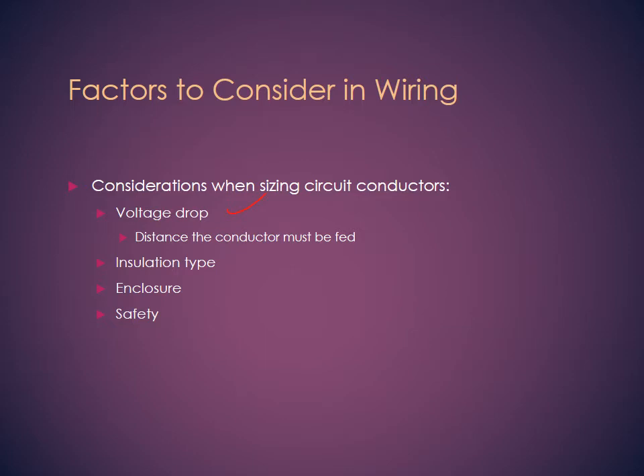We said 14 gauge mostly. Next, voltage drop. Voltage drop depends on the distance of the conductor that must be fed. The longer wire will drop more voltage because R will increase. If you have 120 volts here, for each foot there's a drop. If you go into the table from before, it will give you the resistance for that wire per foot, so you can multiply and know the resistance. And as we calculate the resistance, we can calculate the voltage drop based on the amperage required for that equipment.